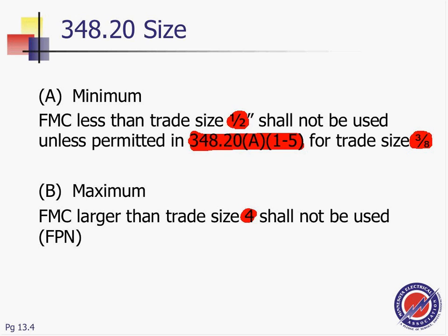That's basically how we look at motors, where you can use it. So it says, for trade size 3/8, enclosing the leads. They have limitations on the trade size 3/8, guys. Then, the uses permitted by A1 through A5. So for that 3/8, here's where they want you to use it. Number 1, using leads of motors, no problem. In lengths not more than 6 feet, utilization equipment, a listed assembly, or tap connection to luminaires as permitted. Manufactured wiring systems, no problem. And in hoistways as permitted in 620. We said that hoistways are not permitted, guys, except there are some exceptions for them. And a ballast assembly to connect to wet luminaires. So really 3/8 is not your wiring conduit. There's a lot of limitation on the 3/8, and there's a table of its own.